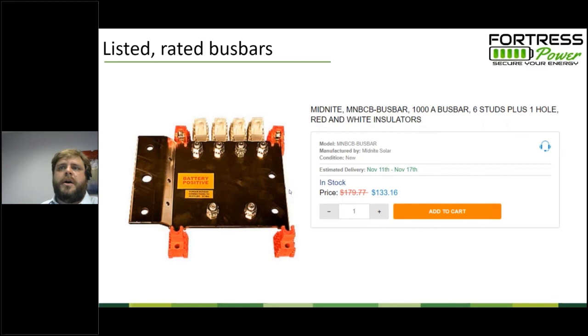High amperage components do cost money. You're going to have to buy more than just the battery. But sometimes building your own box, putting the bus bars in a gutter rather than in their own box, those things can simplify the job site. So, as far as bus bar ratings go from a manufacturer that will give you an actual voltage rating and amperage rating, Midnite is a very popular one. Here pictured is a 1,000 amps bus bar for $133.